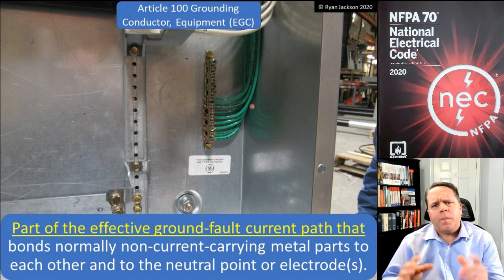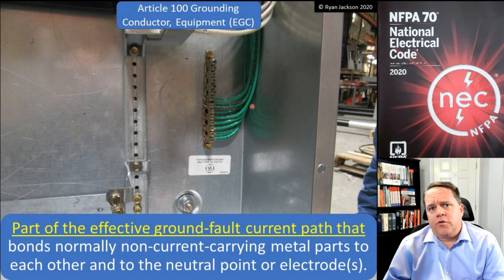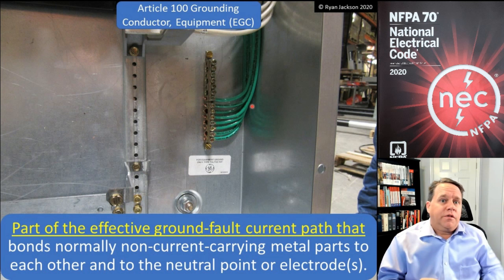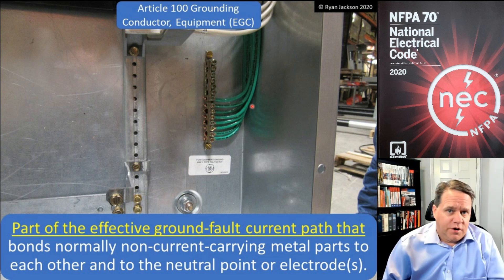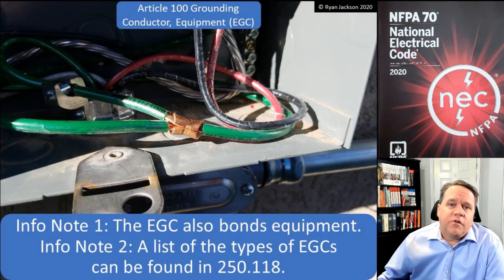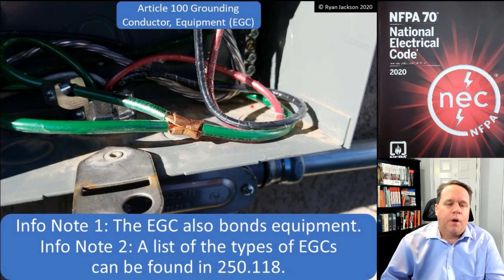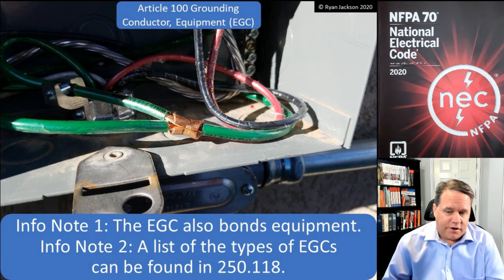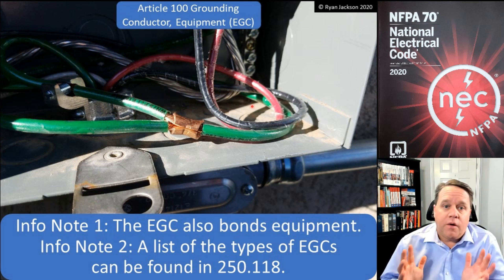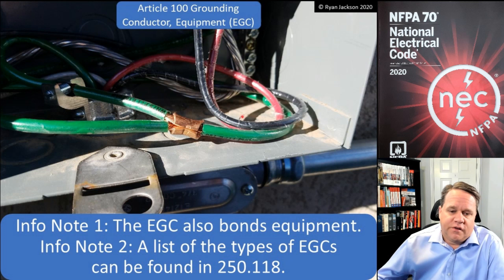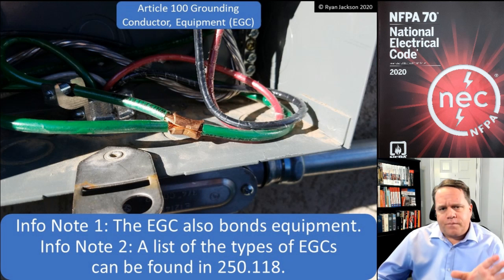So if you change equipment grounding conductor to equipment bonding conductor, you'd have the opposite people stomping their feet saying what about the grounding portion? What they did in the 2008 code is they said it does both — we're not going to call it grounding and bonding conductor. The first informational note says the equipment grounding conductor also bonds equipment; it's not just grounding, it's bonding.